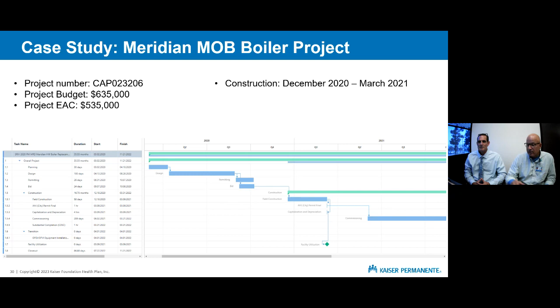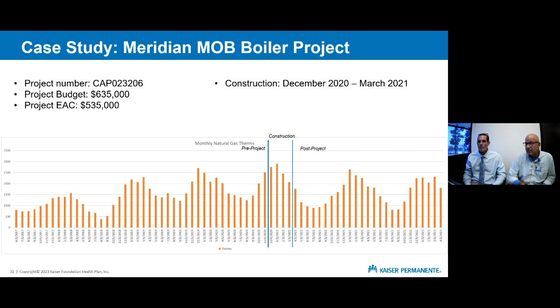This is how we're kind of looking at it, again energy pre and then post. Obviously we didn't include the construction period. It was a very quick, simple project, a 4-month construction period. The OPR did have some good things in it, including reference to Title 24, which has certain energy requirements, but that's really more on boiler efficiency. There were commissioning requirements, and there was a line about a dual boiler variable primary system, meaning someone was really thinking about an energy efficient system.